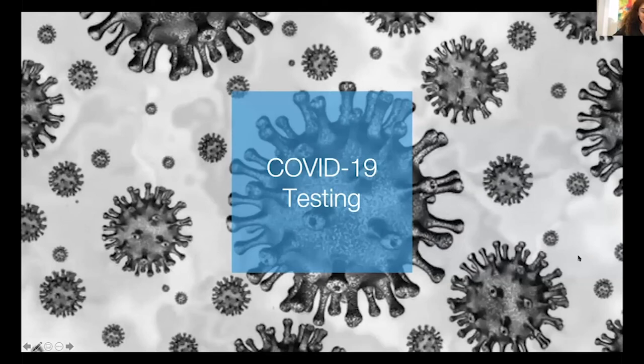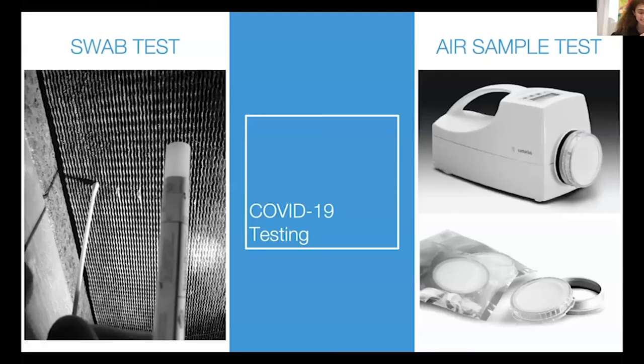Now, before I end, there is COVID-19 testing. There was a gentleman in the previous presentation who asked how we can monitor air quality. Before the pandemic, we had a new trend in sensors. Typically we have temperature and relative humidity, and in many class A office buildings we have CO2 sensors, carbon dioxide sensors. Carbon dioxide is great to tell you the sufficiency of ventilation, but it doesn't work well if you have filters. Filters and carbon dioxide don't match. If you have filters, carbon dioxide low or high is not going to tell you much. But what I want to tell you here is that you can do COVID-19 testing, actual testing.